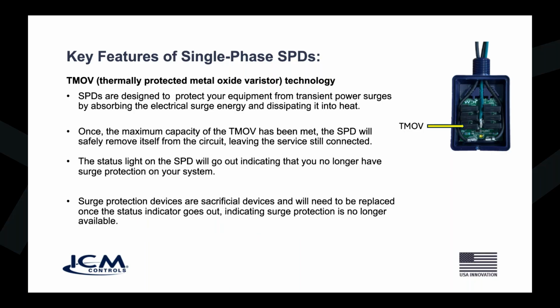So they're going to clamp your voltage at the rating of the TMOV, and ours are about 300 volts. And then it's going to dissipate all the rest of that energy, all that surge that you see on the top of that spike. That's all going to be dissipated as heat. It's going to convert that electrical energy to thermal energy. Once the maximum capacity of the TMOV has been met, then the SPD will safely remove itself from the circuit, but leave you still connected. All right, so if a surge comes in behind it, then of course you're not protected.